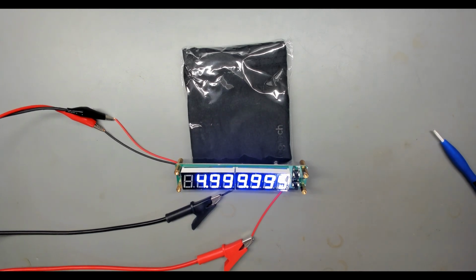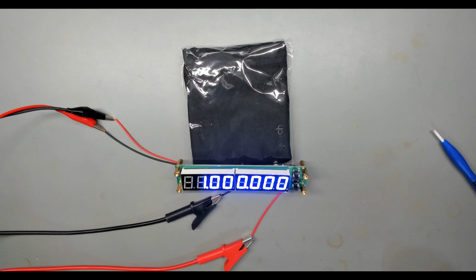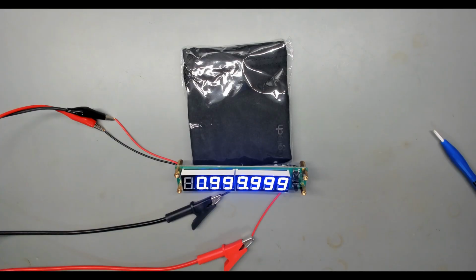Let's take her to 5 and see what she's at now. Okay, at 5 megahertz we are about 5 hertz off. And at 1 megahertz we are almost dead on. It's going back and forth. So that's not too bad. We made an improvement there. Run back up. Where do we end up at 30?